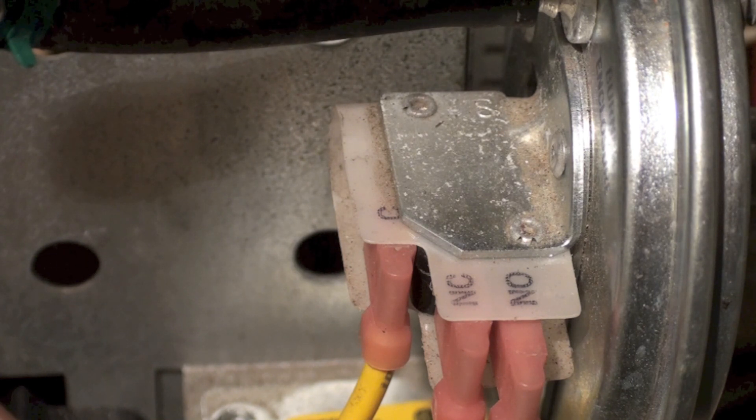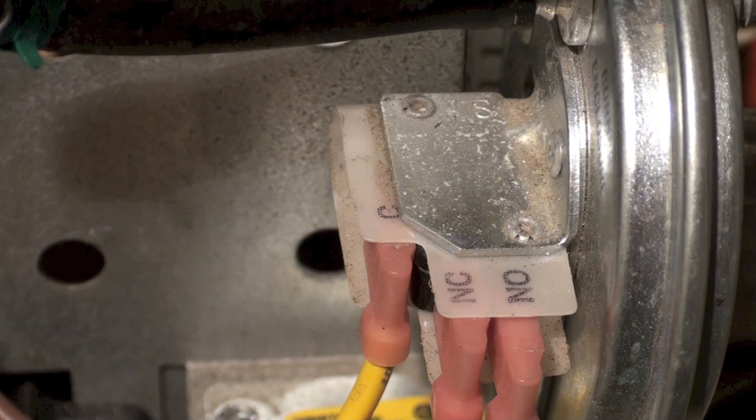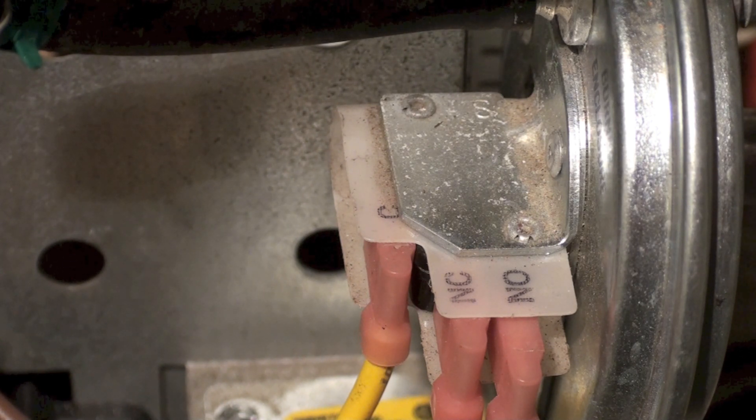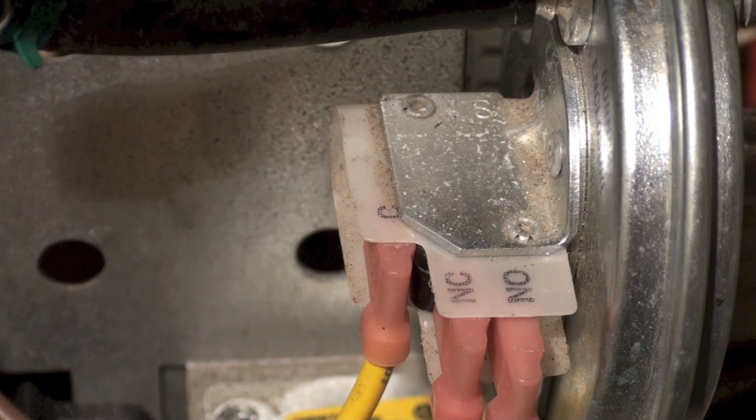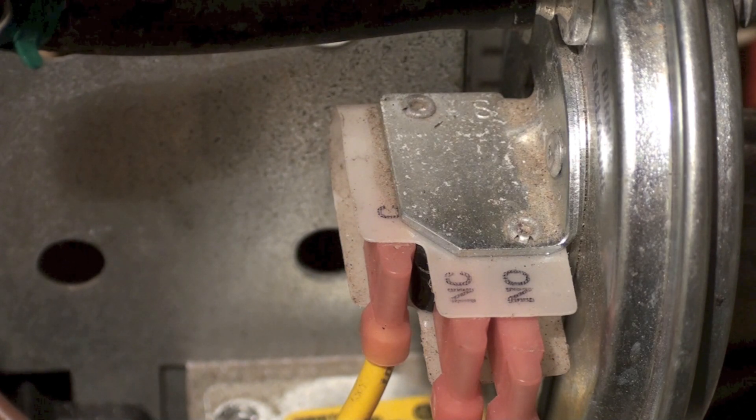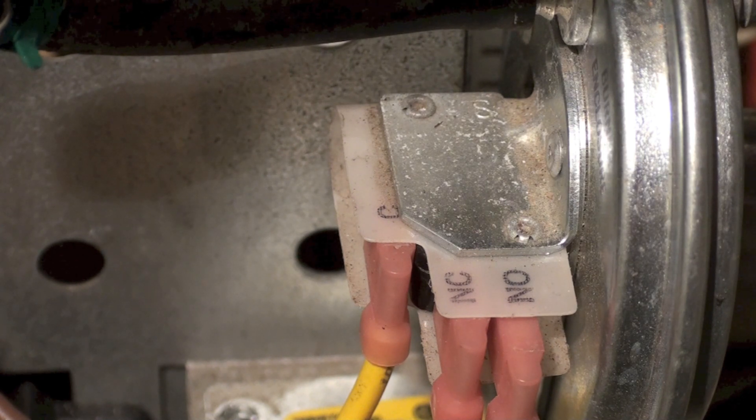So if this was a single pole single throw it would be a normally open switch, and then it would make when the inducer came up to speed. The problem with that is if the pressure switch has stuck into the normally closed position, then there's no way to determine that happened. So the furnace would simply start off with a pressure switch already closed, and even if the inducer failed it would be closed, so then the furnace would fire off.